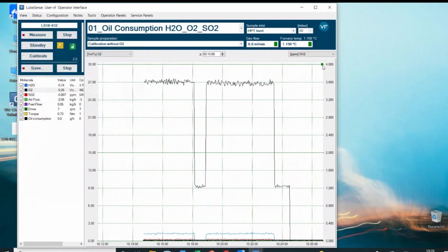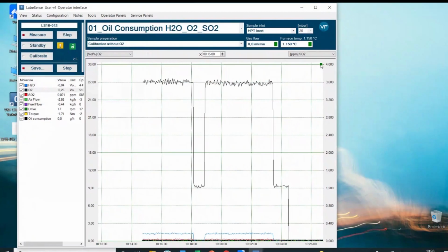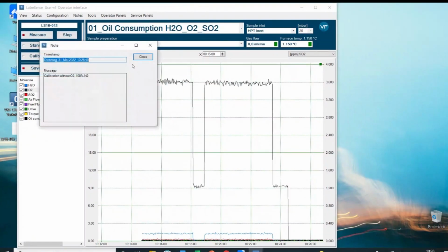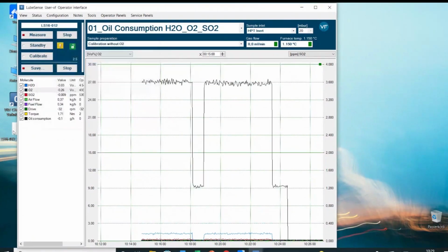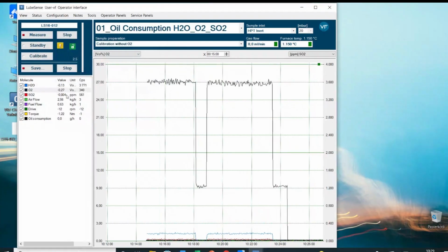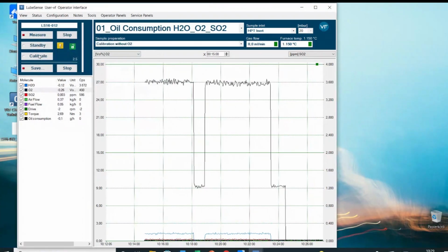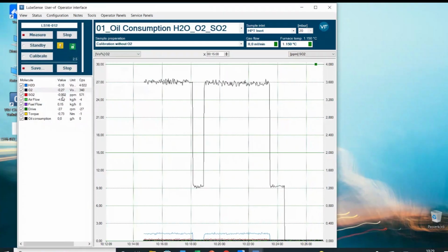And you see these notes will be attached into the timeline, and I can look at them either by double clicking here or later on also in the saved file to see what's going on. So the next step would be to establish the background level. I'm doing all of this manually right now, just for you to get an impression of what is being done. The automatic calibration routine will do all of this by itself.